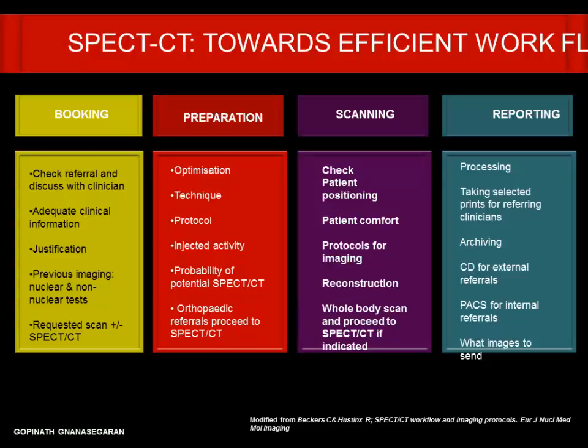Coming to how to deliver the SPECT-CT service: the most common problem is booking. When booking a patient, you need to check the referral, discuss with the clinician exactly which part of the body they want for SPECT-CT, and ensure adequate clinical information for maximum diagnostic impact. You cannot do SPECT-CT in all patients, and it is mandatory to look at all previous nuclear and non-nuclear imaging as a habit. For orthopedic indications, a local protocol can be modified so all patients have a two-phase bone scan followed by SPECT-CT as routine.